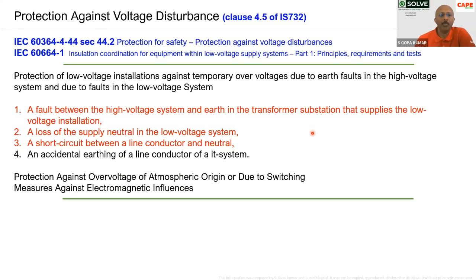Any voltage which is more than these limits, more than 253 volt between line to neutral or line to earth, or more than 440 volt line to line, is termed as a temporary overvoltage. Temporary overvoltage, if it persists for a longer time, your equipment will fail.